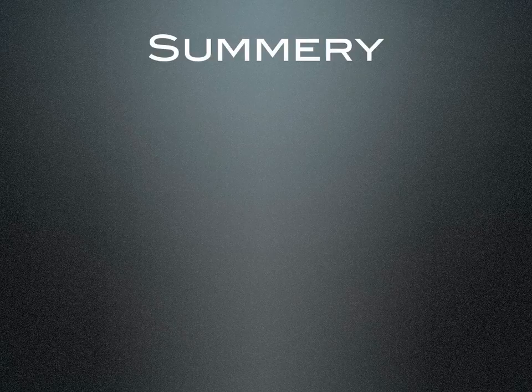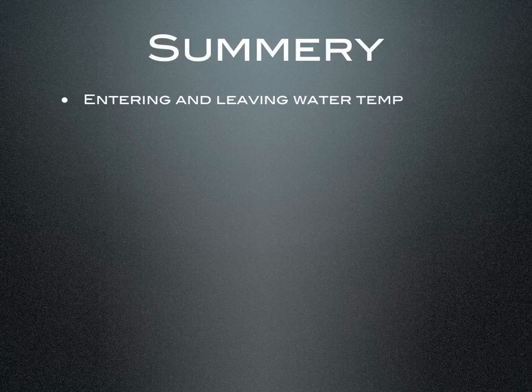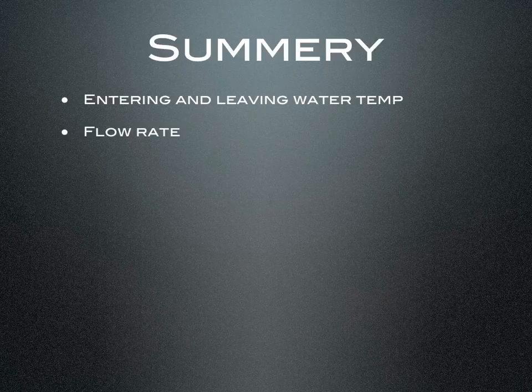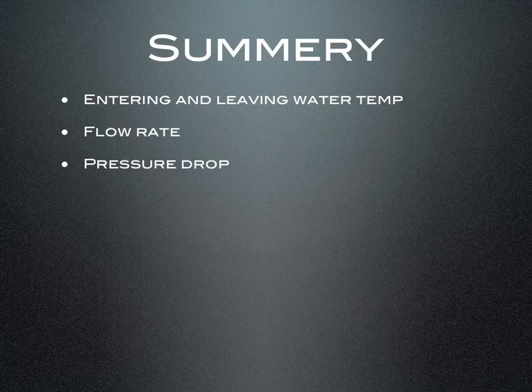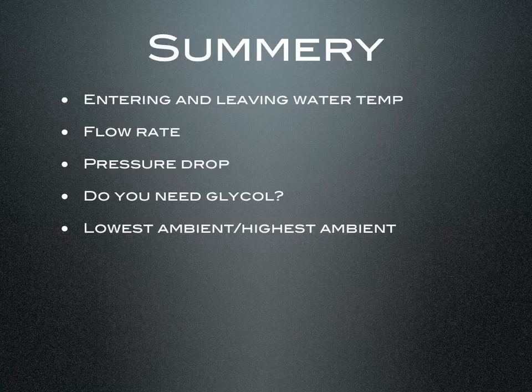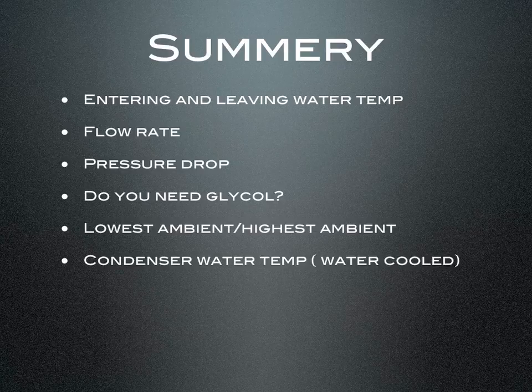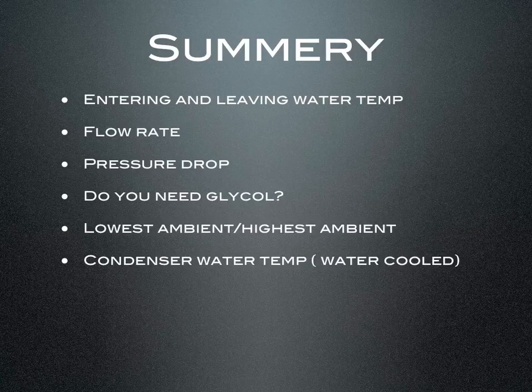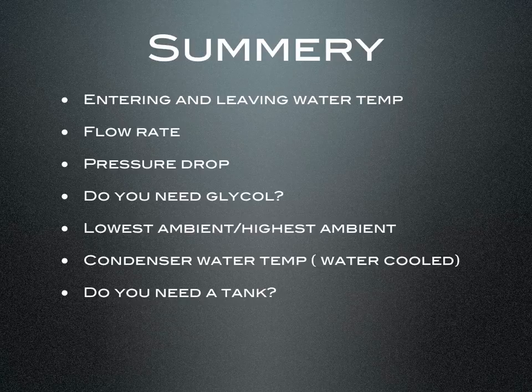Let's summarize what we need to know to size a chiller properly. First, you need to know the entering and leaving water temperature to your equipment, what flow rate you need, and the pressure drop through your piping and equipment — that will help select your pump. You need to find out if you need glycol, and what the lowest and highest ambient temperature is where the chiller will be placed. If you have a water cooled chiller, find out what the condensing water temperature is — that's the temperature of the fluid from the building water or cooling tower. And determine if you need a tank; if there is not enough fluid in the piping, you need to go with a tank.